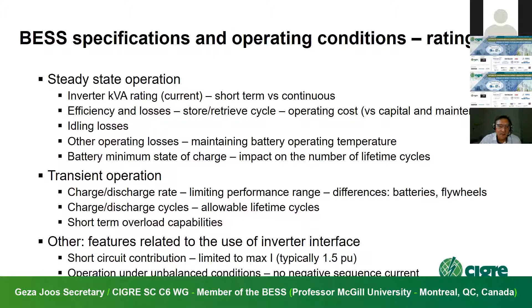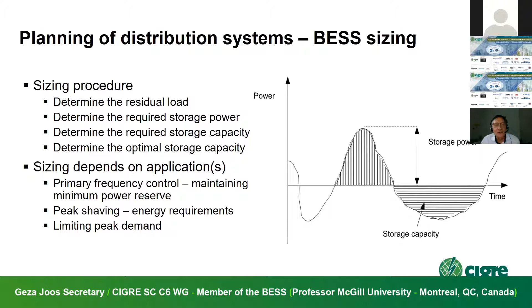So this is an example of primary frequency control. You can also size it for peak shaving, and then you have to size it for the maximum power that you need. You have to decide on the kilowatt rating, and you have to decide on the kilowatt hour rating. And there are many examples where the kilowatt and the kilowatt hour are not the same. They're the same if it's a 1 hour rating, but anything else is possible. So here is a list of sizing constraints: primary frequency control, accounting for load growth, and so on.